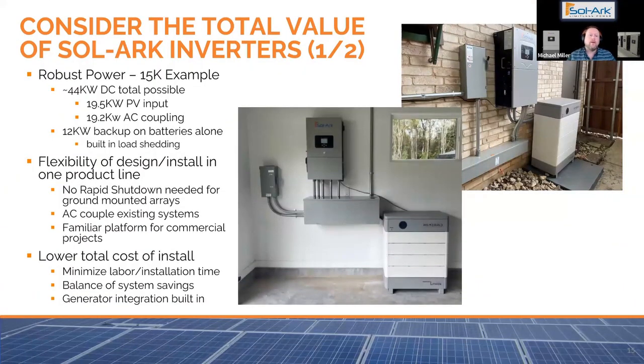Now consider the total value of the Sol-Ark inverter. So robust power, the 15K, for example, you have the ability to put 19.5 kilowatts of DC solar on it, and you can AC couple 19.2 kilowatts of solar, which is the AC rating. So essentially you could have up to 44 total DC coming to one inverter. So that is a heck of a lot of power. And maybe you have an existing system, maybe you want to just have one backup unit. We do offer 12 kilowatts of backup on batteries alone, and you do have built-in load shedding in a grid outage situation or based on the battery charging state.